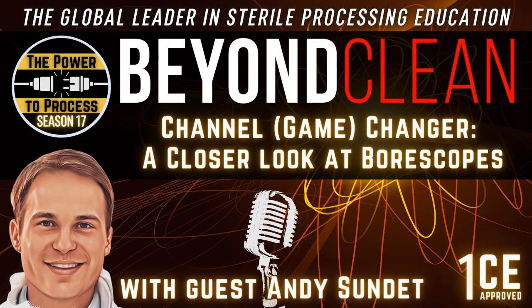If visual inspection is going to be important, make sure that the workstation has ample space. Justin, you said things like setting trays on a borescope. I know a ton of stuff goes on in the department, and it's tough to always have a clean workstation, but some of these things can help protect the borescope and also make for a lot easier and quicker inspection. And that's what we're trying to do. We don't want to delay the whole process. We want you to be inspecting, getting done with the device, moving on to the next one.